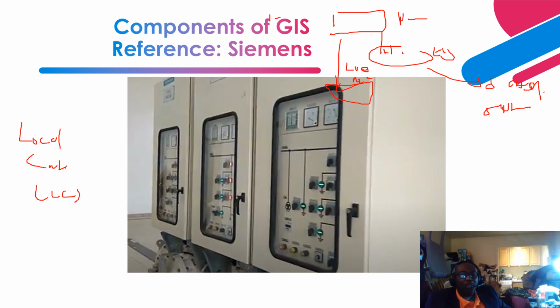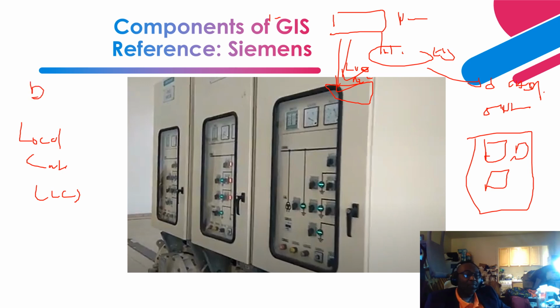Right. Okay, so close to this one should be a protective relay panel, right? That has all the protective relays that protects your line feeder, right? So your line feeder, you can have a differential protection, right? You can have a distance protection if you have a transmission line on that line feeder, right? This section is your bus. Usually, because the GIS is much more compartmentalized and filled, usually there is no bus differential, unless of course the customer specifically indicates that they want a bus differential, but most of it are not. The GIS don't have a bus differential, but rather have a line protection for the line side.